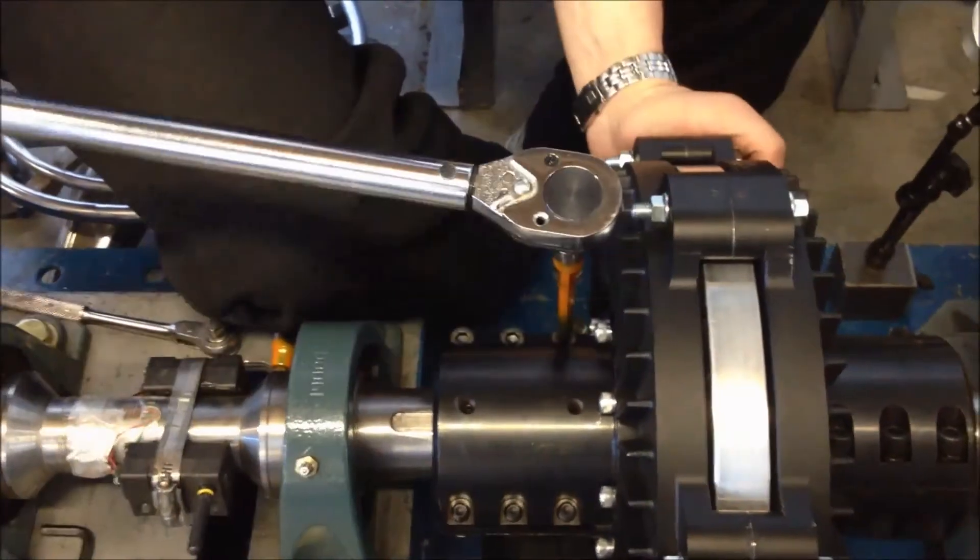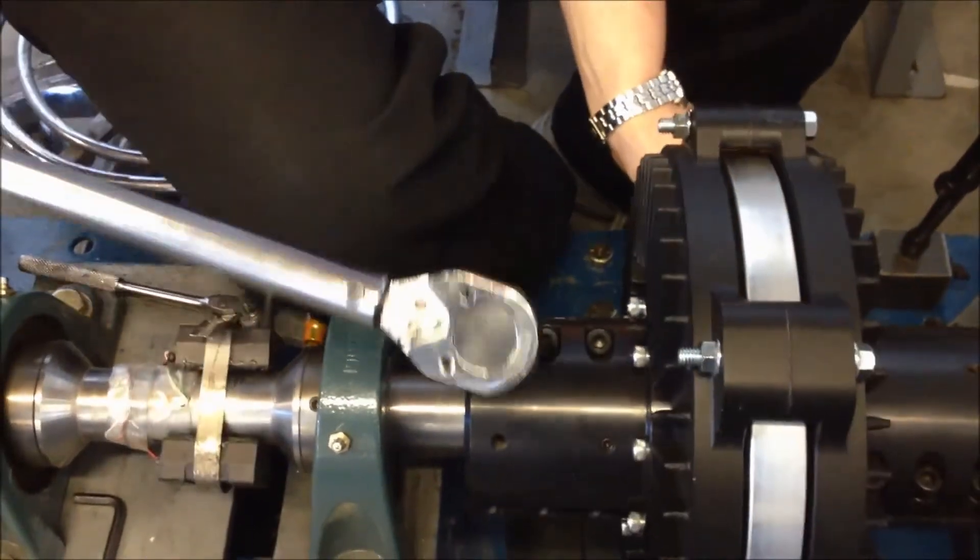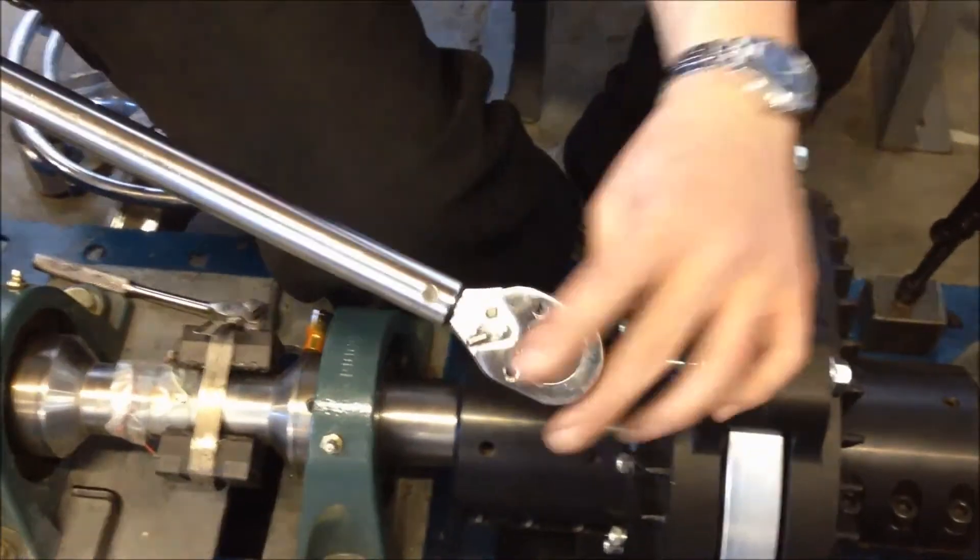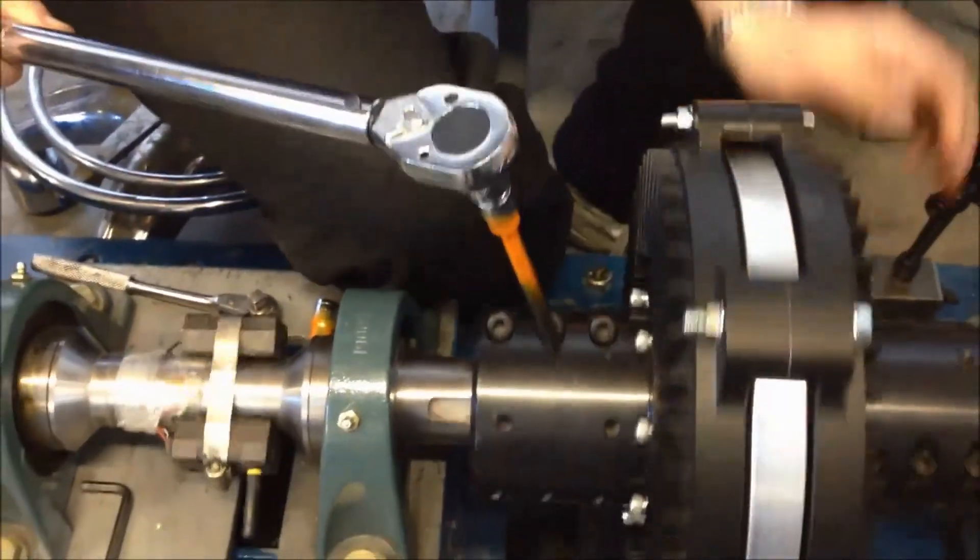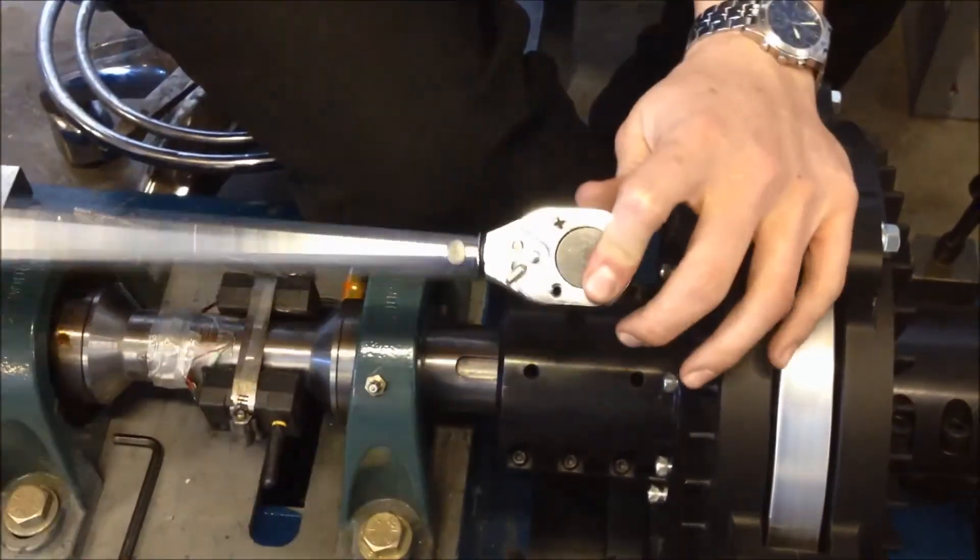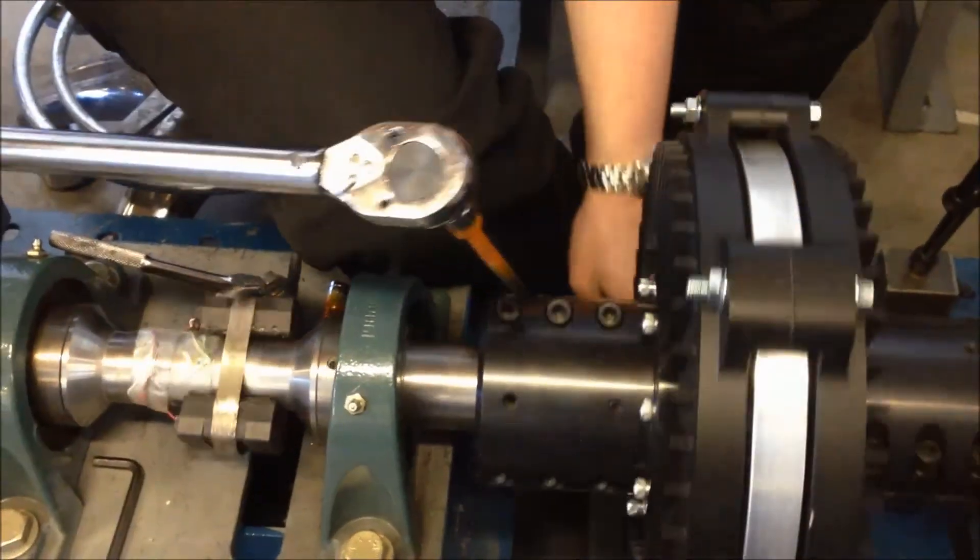Tighten the six clamp bolts on the load side hub in an alternating pattern. Torque the bolts to the specified torque outlined in the instruction guide supplied with the FSC coupling. Tighten the two set screws over the keyway last. Repeat this procedure for the motor side hub also.